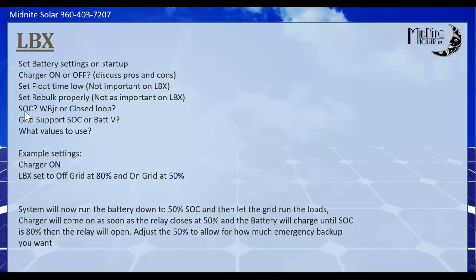Other than that, it's all the same stuff: state of charge, are we doing closed loop or open loop state of charge, do we prefer to use battery voltage to trip this off and on like we did on grid support? That's up to you, on how the system operates, what's most balanced. If you're doing closed loop, like our PowerFlow 5, state of charge is definitely the way to go. If you're doing a set of lead acid batteries and you don't feel you've got the Whiz-Bang Junior dialed in perfectly yet, do battery voltage. Set it up on battery voltage and tune it in how you want.